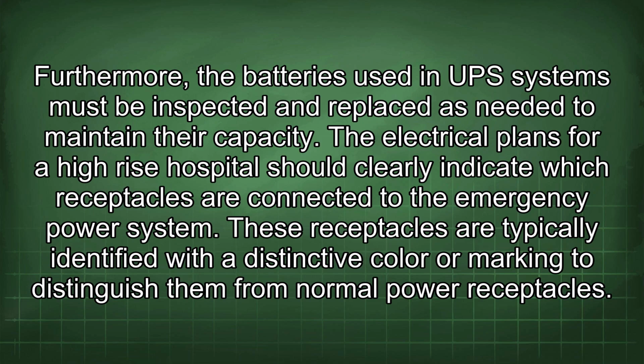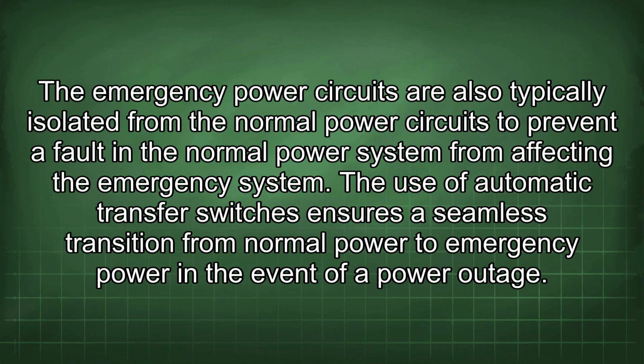The electrical plans for a high-rise hospital should clearly indicate which receptacles are connected to the emergency power system. These receptacles are typically identified with a distinctive color or marking to distinguish them from normal power receptacles. The emergency power circuits are also typically isolated from the normal power circuits to prevent a fault in the normal power system from affecting the emergency system. The use of automatic transfer switches ensures a seamless transition from normal power to emergency power in the event of a power outage.